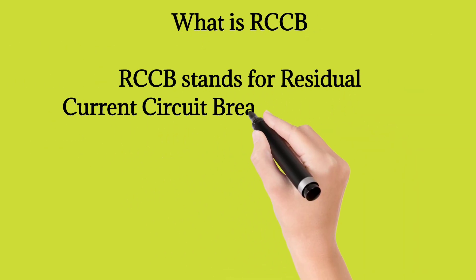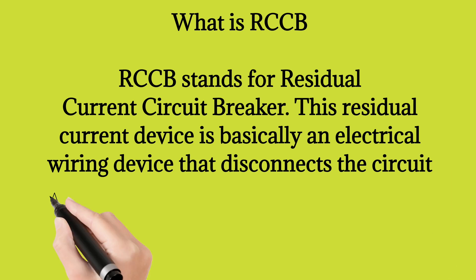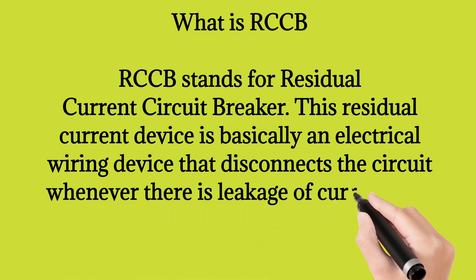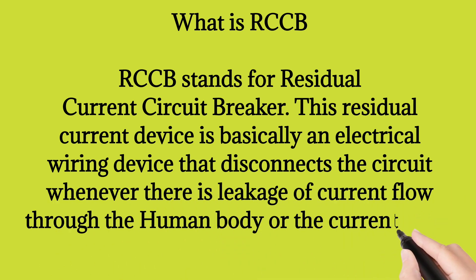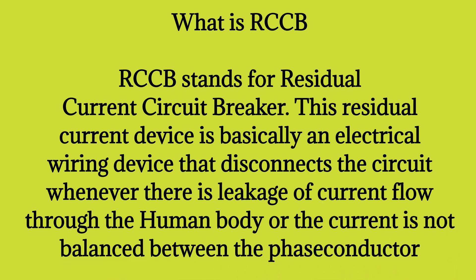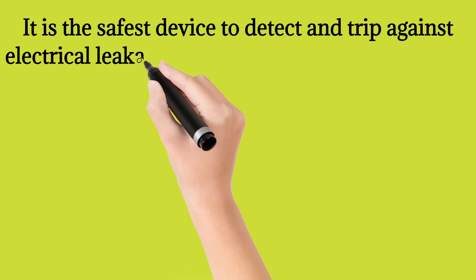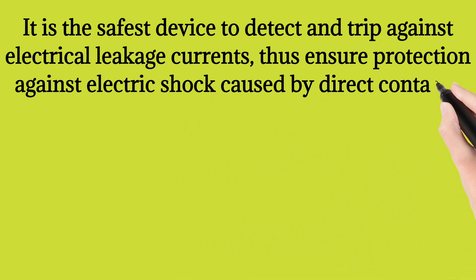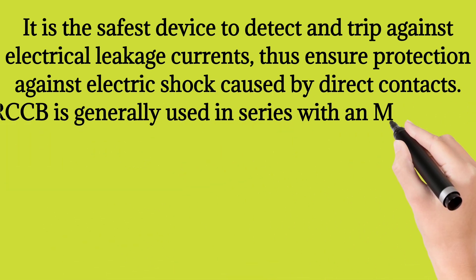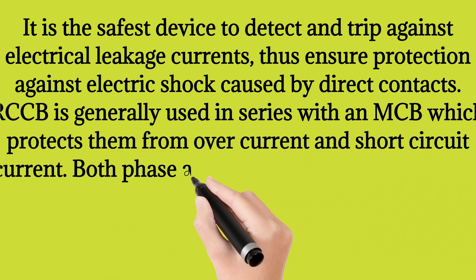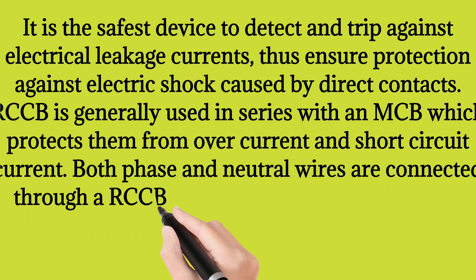What is RCCB? RCCB stands for Residual Current Circuit Breaker. This residual current device is basically an electrical wiring device that disconnects the circuit whenever there is leakage of current through the human body, or when the current is not balanced between the phase conductors. It is the safest device to detect and trip against electrical leakage currents, thus ensuring protection against electric shock caused by direct contacts. RCCB is generally used in series with an MCB which protects against overcurrent and short circuit current. Both phase and neutral wires are connected through an RCCB device.